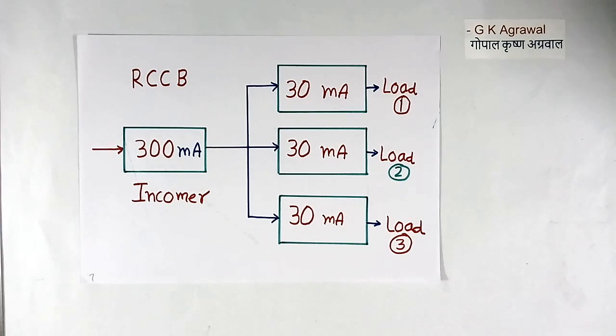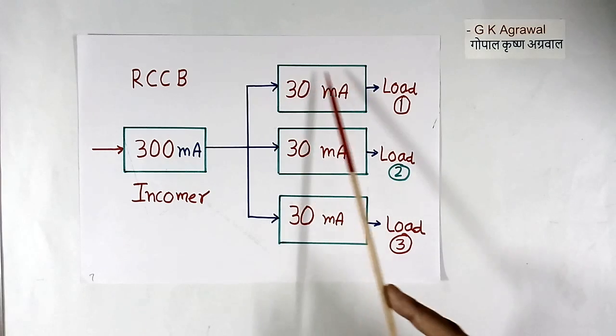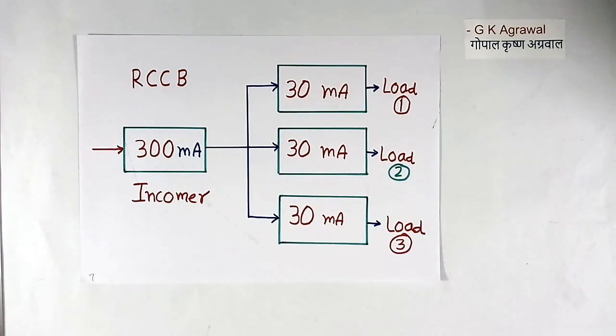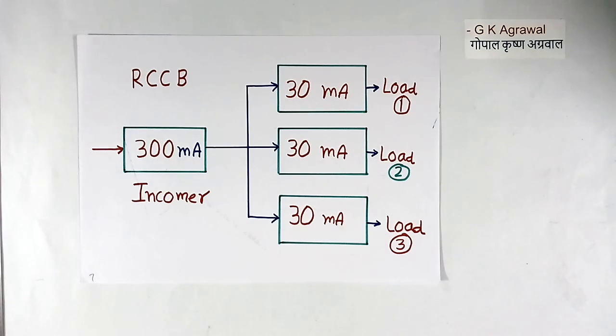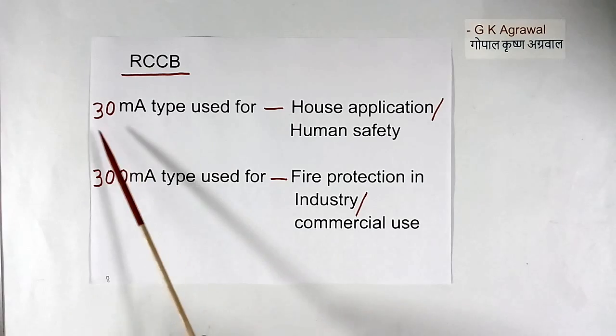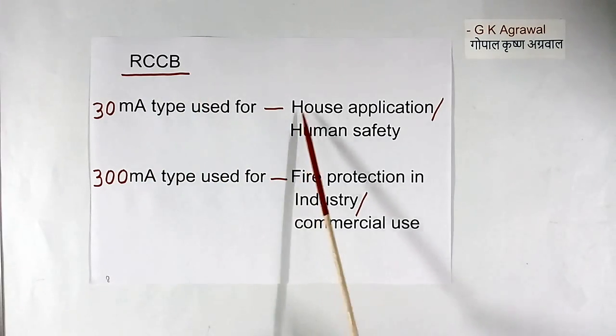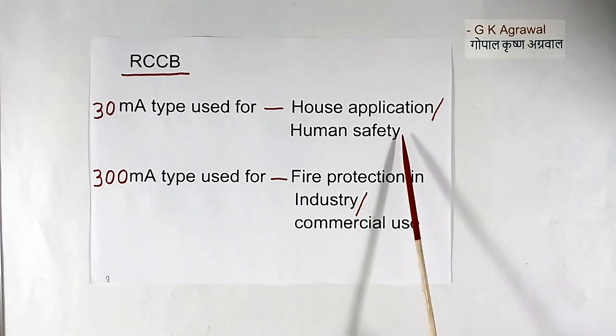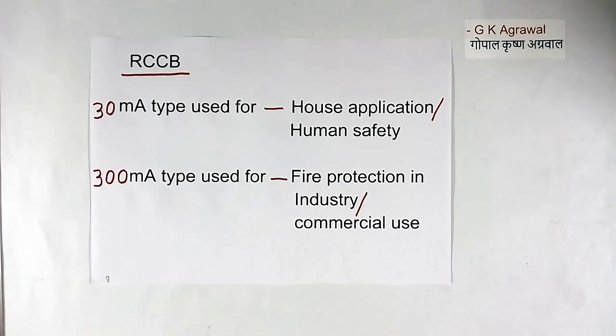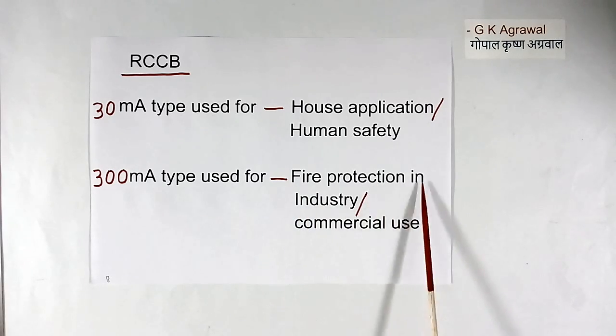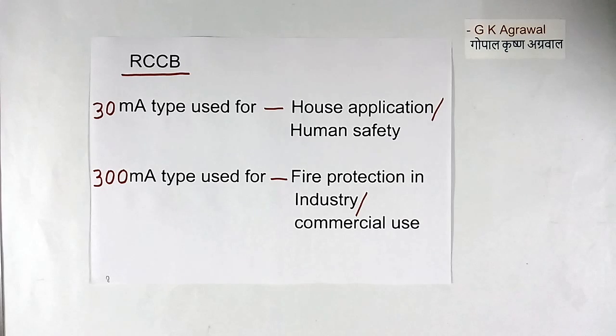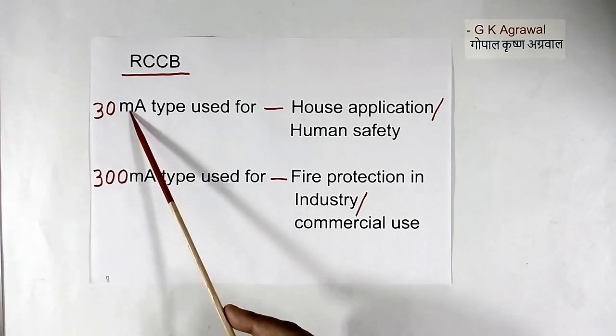Here I have shown 3 sub-RCCBs; there may be 4 or 5. These 30 mA RCCBs will provide protection to humans. If we have a big building with many flats, the incomer may have the 300 mA type, and every flat may have a 30 mA type RCCB. The 30 mA type RCCBs are used in houses for human safety, to protect humans from electrical shock. The 300 mA type RCCB is used for fire protection in industry and commercial buildings, or if we have the frequent tripping problem. But then both types will have to be used.